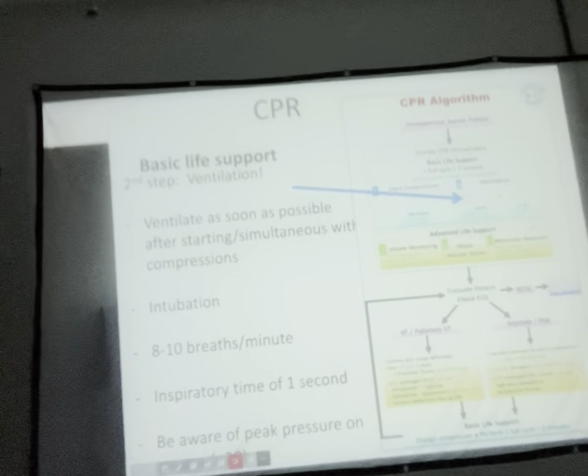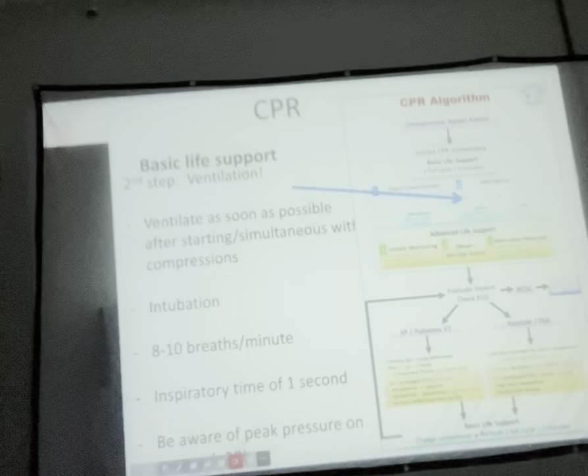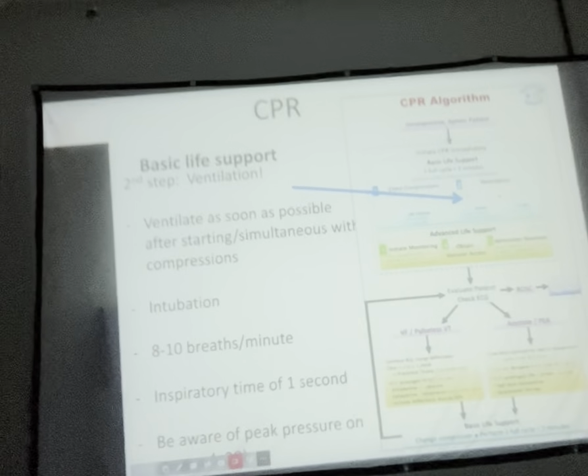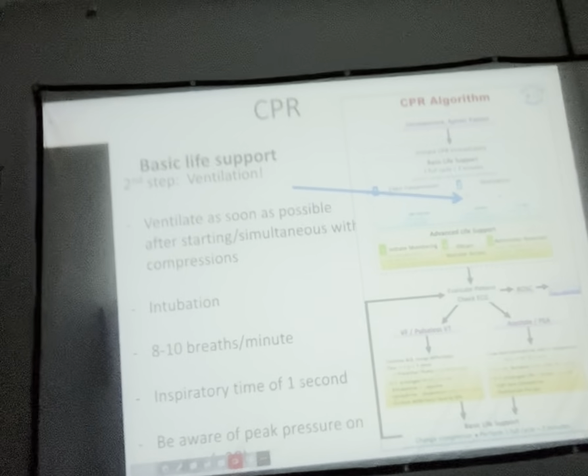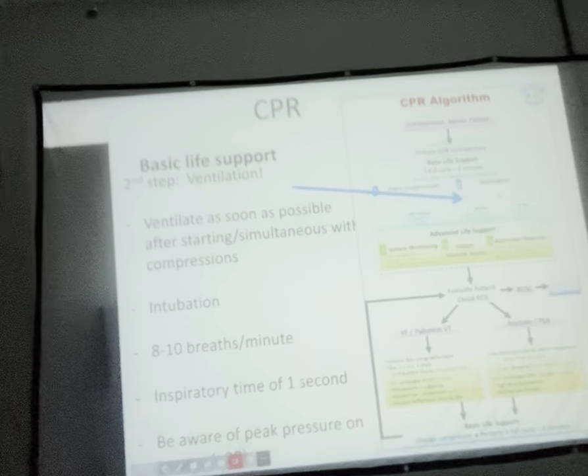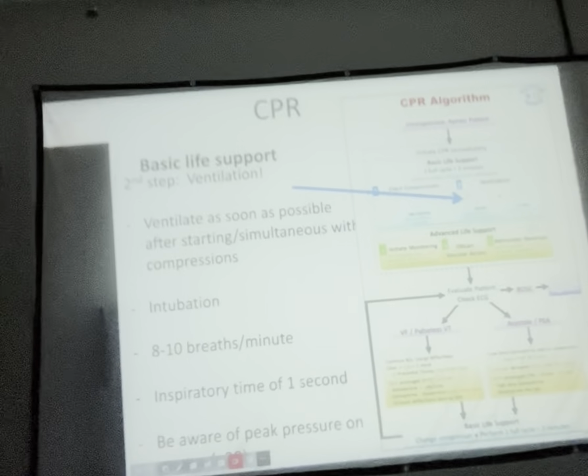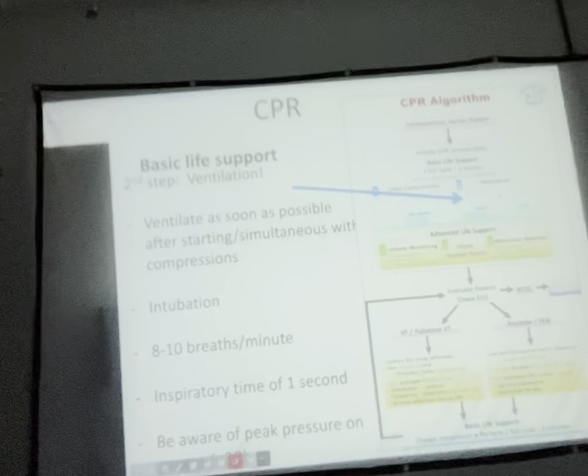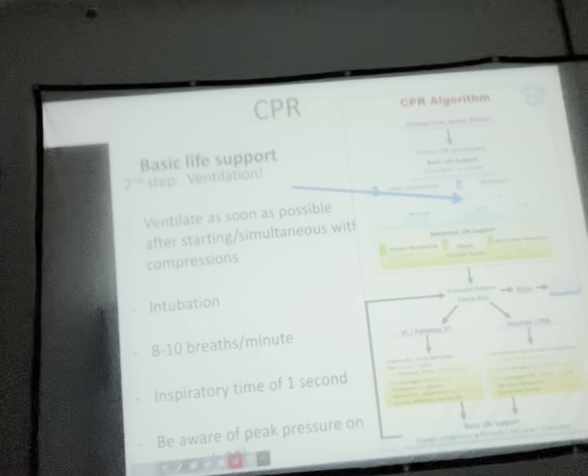One important thing is to be aware of peak pressures. Most of the ambu bags have a cracking pressure where you'll hear that noise if you start to go over 20 centimeters of water in a breath. So the ambu bags have a safety that way. When you're doing breaths off of an anesthesia machine, be cognizant of the manometer and make sure you're not going over 20. And certainly there are times when you'll give a breath and someone goes to do a compression at the same time and it'll shoot up higher than that. That's inevitable, but don't stress about it too much. Just try to be aware of it in general.